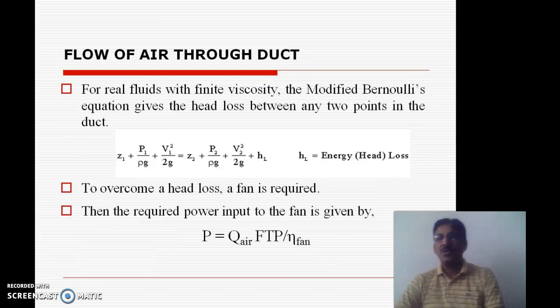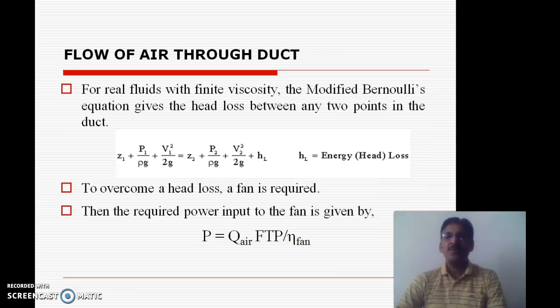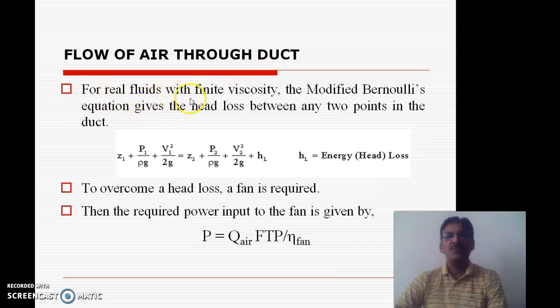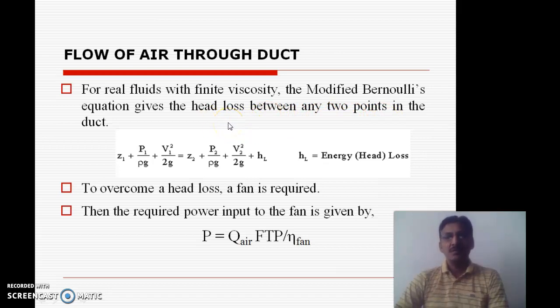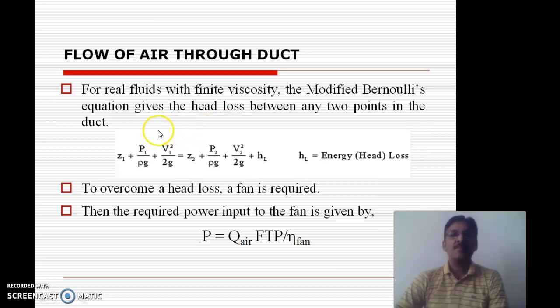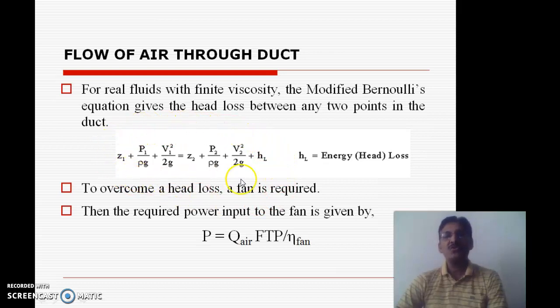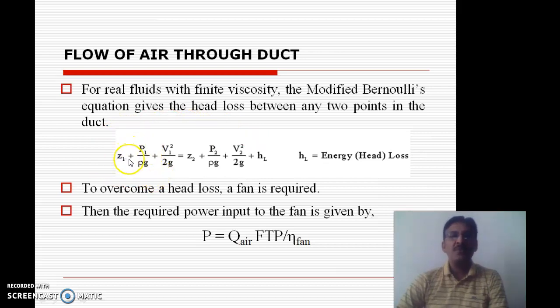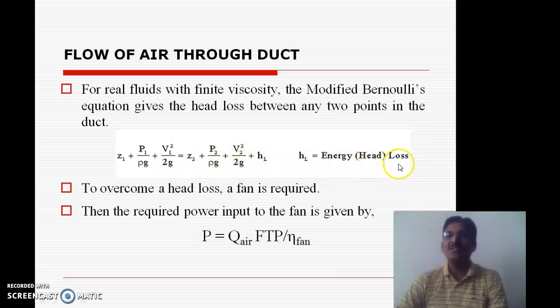Before going to the design of any air distribution system, it is necessary to study the basic fundamentals of duct systems — that is, the flow of air through a duct. For a real fluid with finite viscosity, the modified Bernoulli's equation gives the head loss between any two points in the duct. The equation is: Z1 + P1/ρg + V1²/2g = Z2 + P2/ρg + V2²/2g + HL, where HL is the energy loss or head loss.